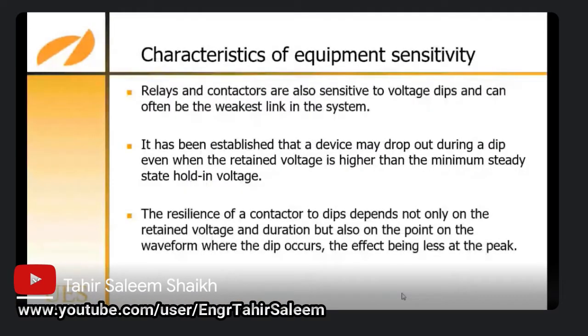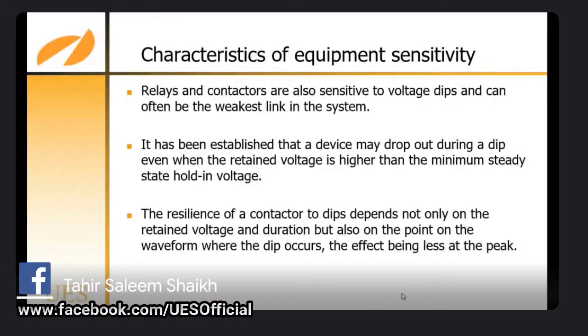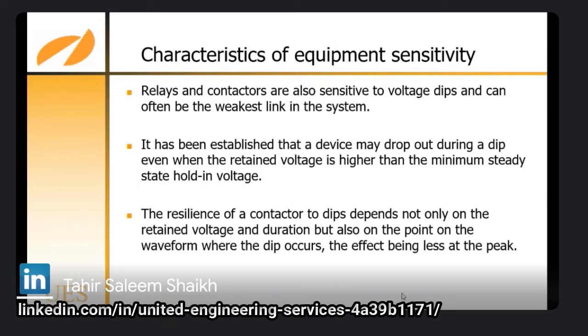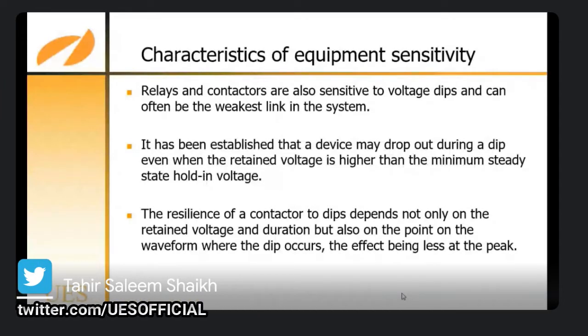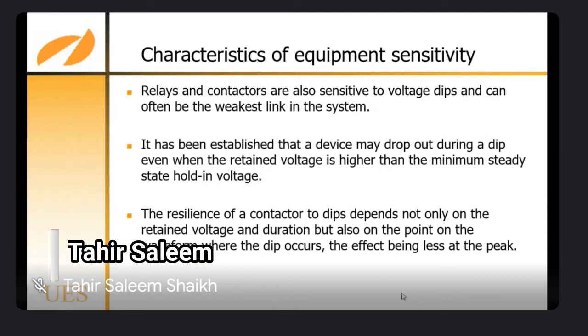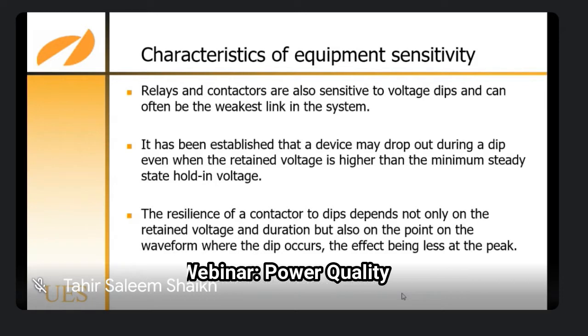Relays or contactors are also sensitive to voltage dips and can often be the weakest link in the system. It has been established that the device may drop out during a dip even when the retained voltage is higher than the minimum steady-state holding voltage. The response of the contactor to dips depends not only on the retained voltage and duration but also on the point on the waveform where the dip occurs, the effect being less at peak.